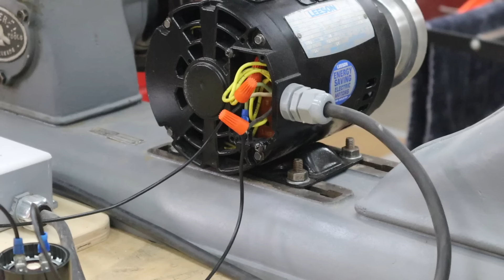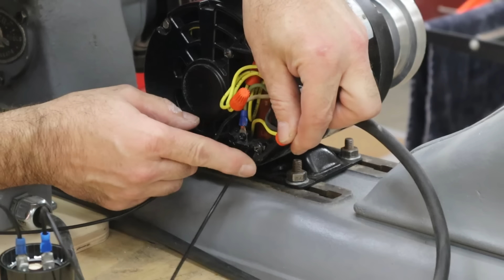Now, a power factor, here we go. I'm just going to take off my electrical tape here, which I put on to make sure that there weren't going to be any sparks during my demonstration. Now let's see here, where's the end? Oh, here we go. Now, when we wire in a capacitor for power factor correction, we wire the capacitor in parallel with the motor. So if we take a good look at these leads, you'll see here is the hot or the black conductor as well as the neutral. And so I've got two leads running in parallel.